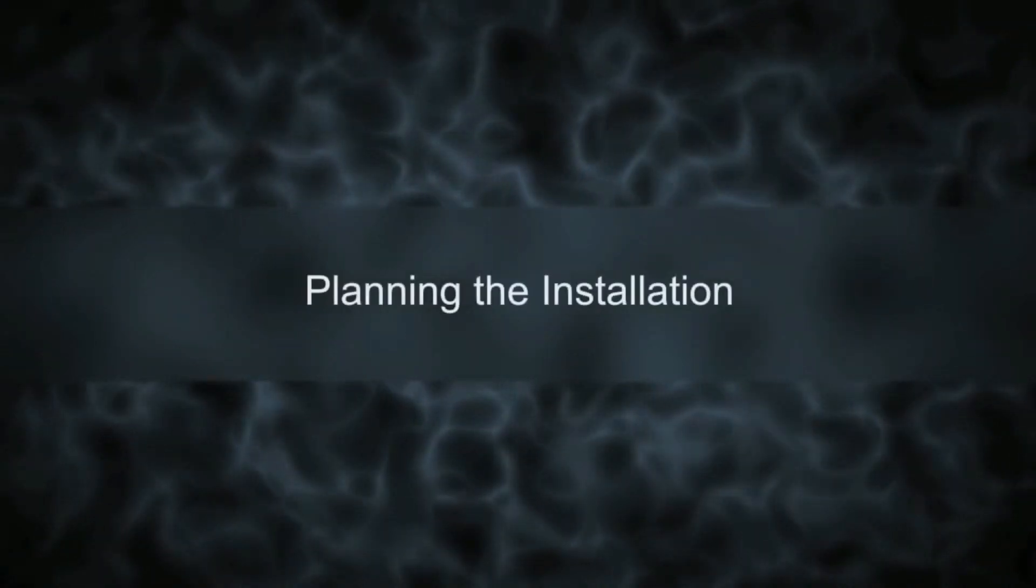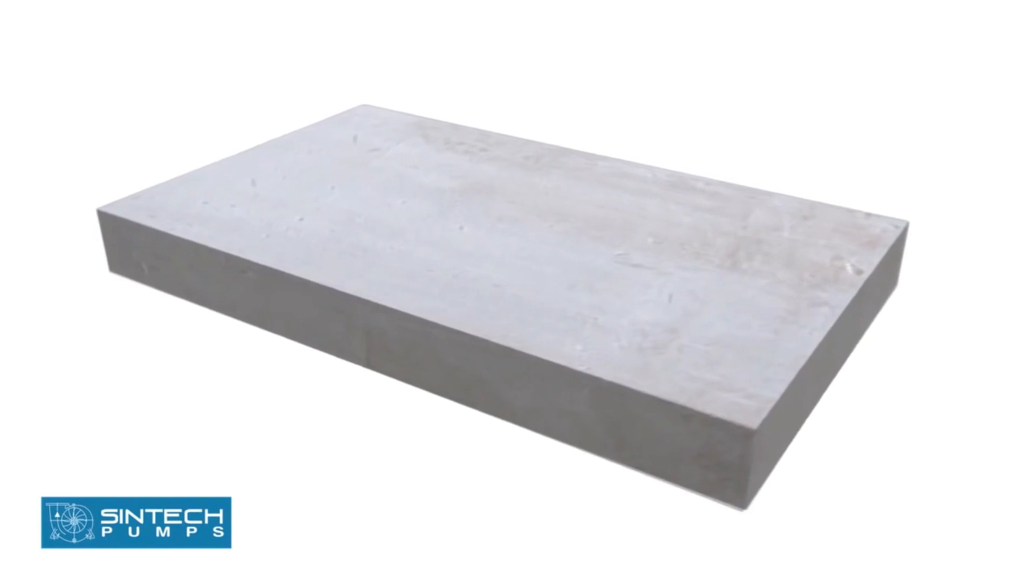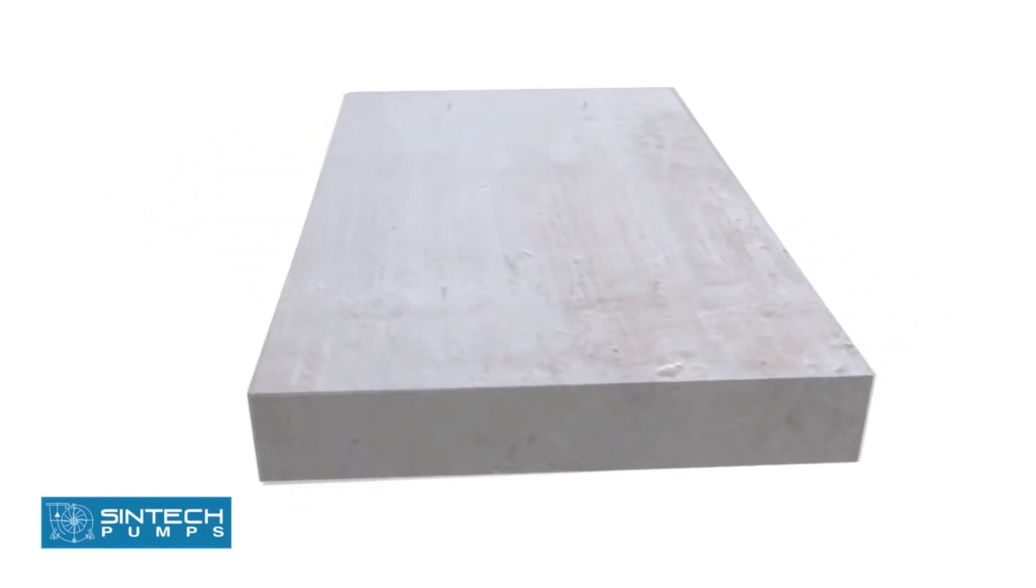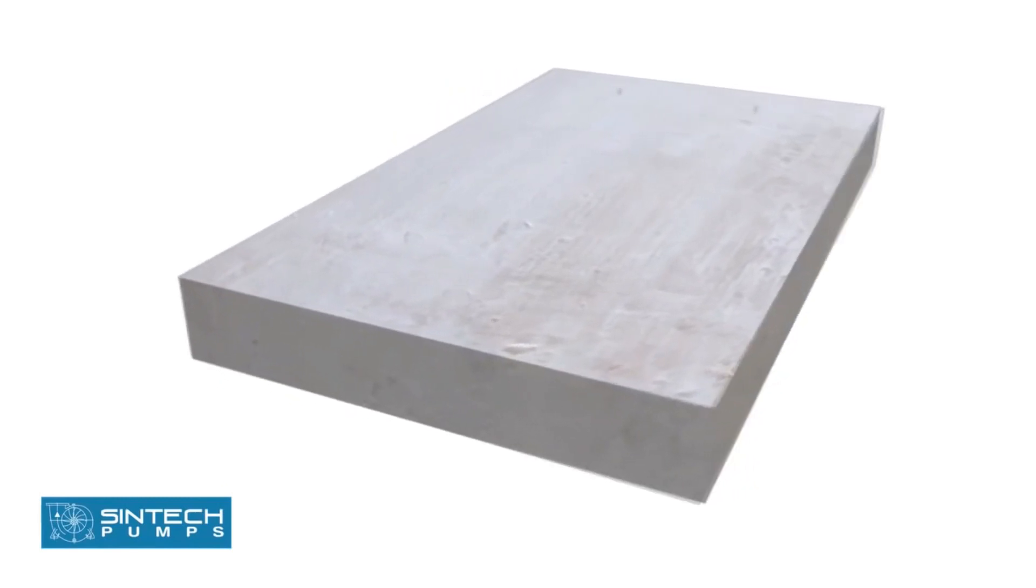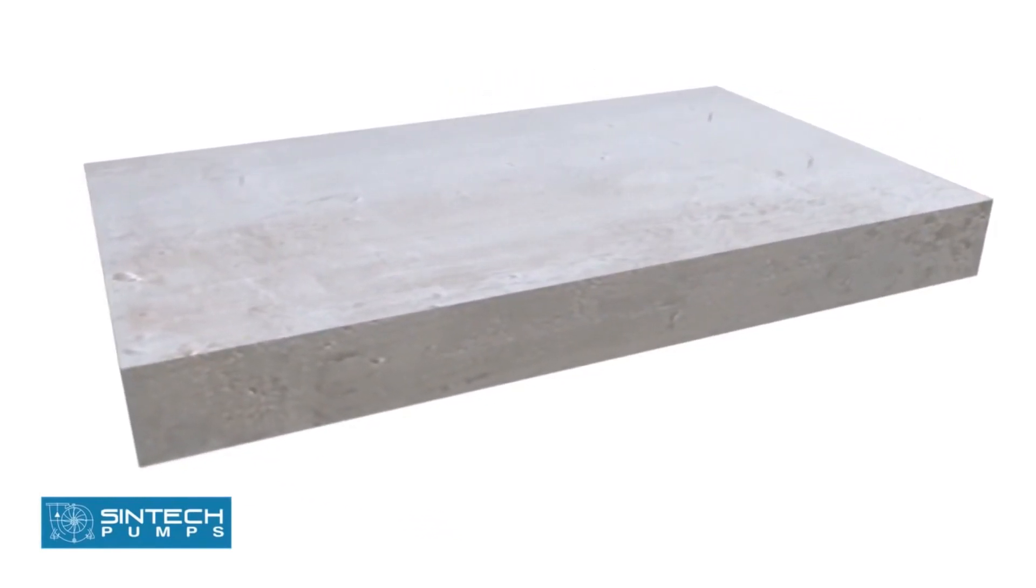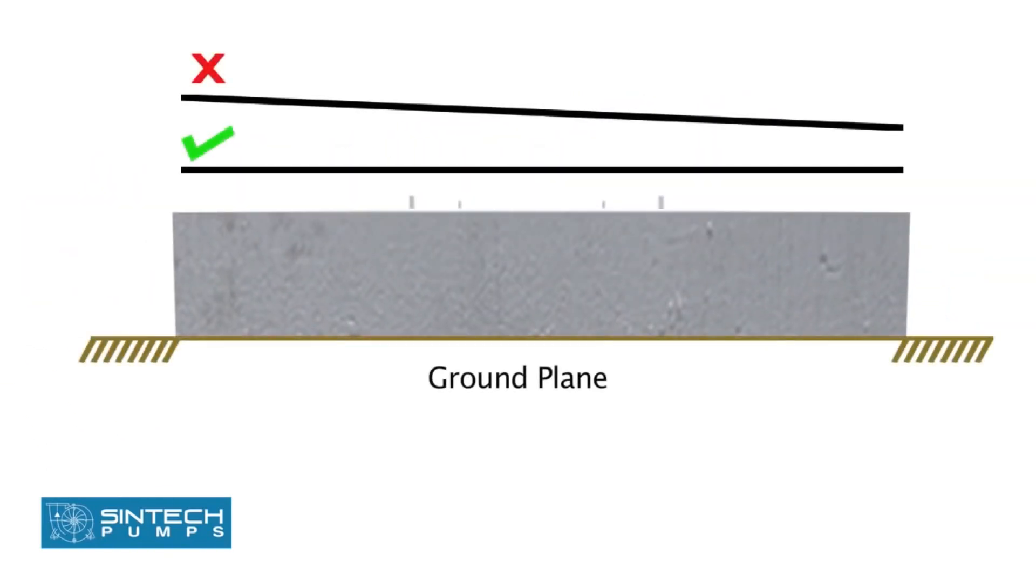For further information, you can email your queries to service@sintechpumps.com. Planning the installation: before installing the pump, ensure that the foundation on which the pump will be placed is prepared well. It has to be sufficiently substantial enough to take the weight of the pump and absorb any possible vibrations from it. The foundation has to be absolutely straight without any inclination or tilting on any side.